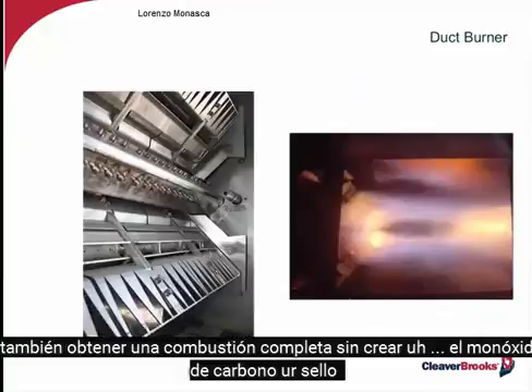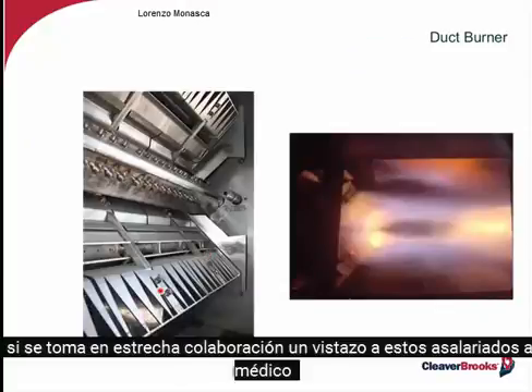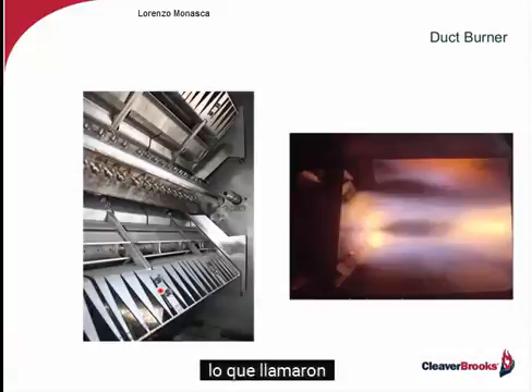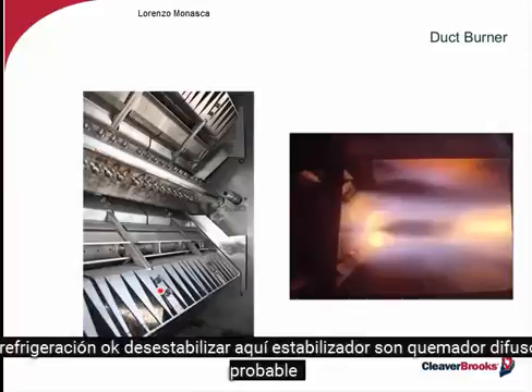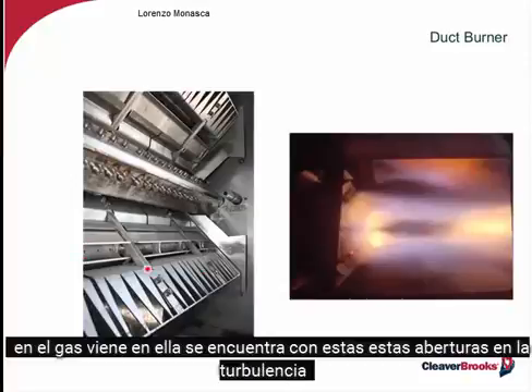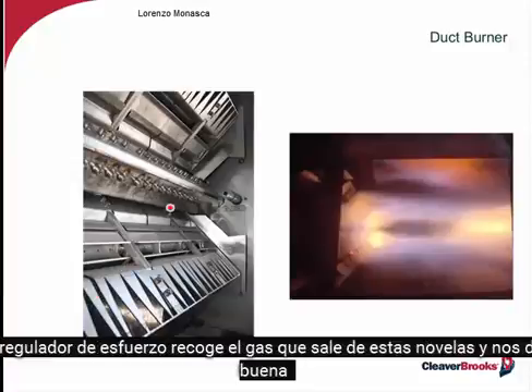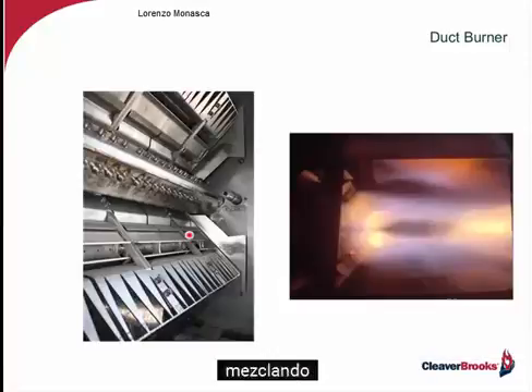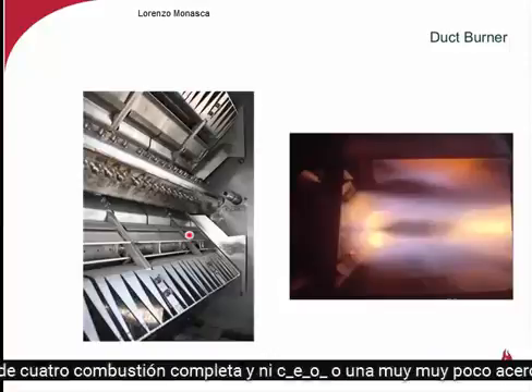If you take a look closely at these duct burners, you have what they call stabilizer cooling. These stabilizers are like a diffuser on a burner. As the gas is coming in, it comes across these openings and it turbulates. As it turbulates, it picks up the gas coming out of these nozzles and gives us good mixing for complete combustion and no CO, or very, very low CO.